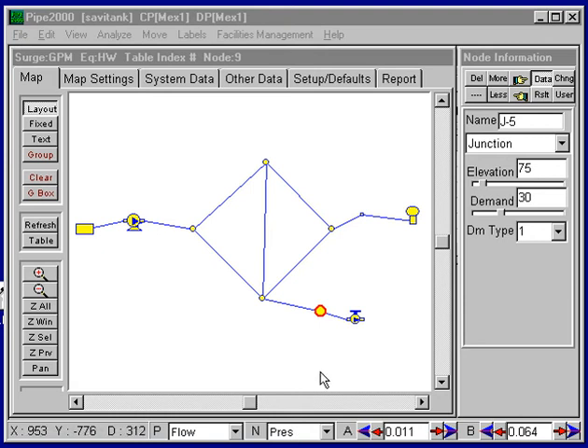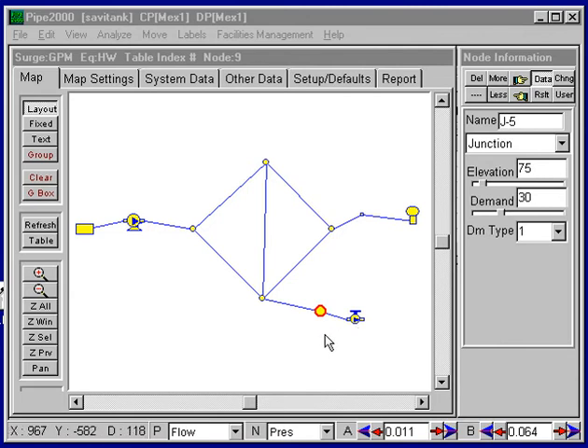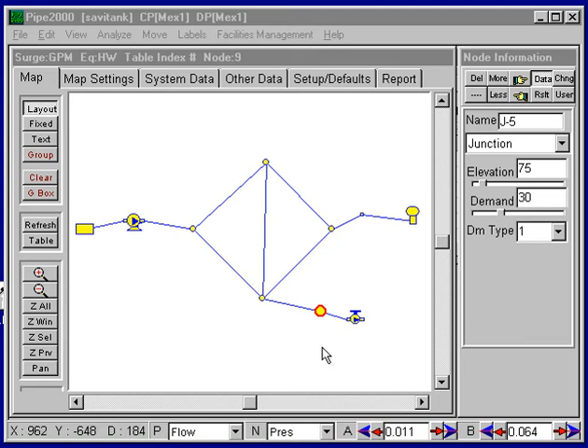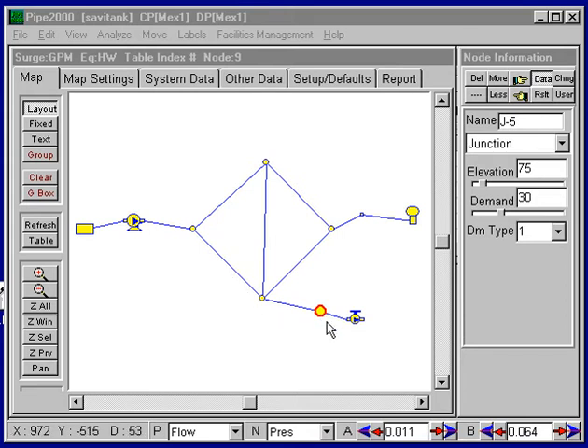In a previous video we developed the surge analysis for this problem. We shut down a valve in a couple of seconds and it produced a fairly severe transient that was propagated throughout this system. In this presentation we want to discuss the use of surge control devices, and at this point we want to attach a surge control device that will protect the rest of the system from this surge.